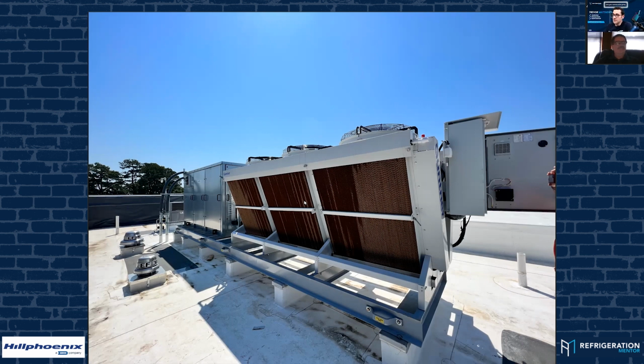But okay, so this is cool. This is important to understand, because now you not only have the high pressure valve and the flash gas bypass valve, but now you have water for adiabatic. You get the fan staging up and down. When you hit a certain percentage of the fans, you hit the certain temperature and relative humidity. That's when it activates. It's just a solenoid that opens up and starts to feed. It's actually a modulating valve, and it meters the flow. Okay. It's like it's a Belimo valve. Okay. And does that measure the gallons per minute, or just?